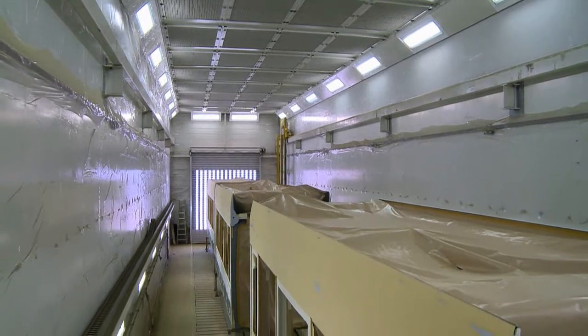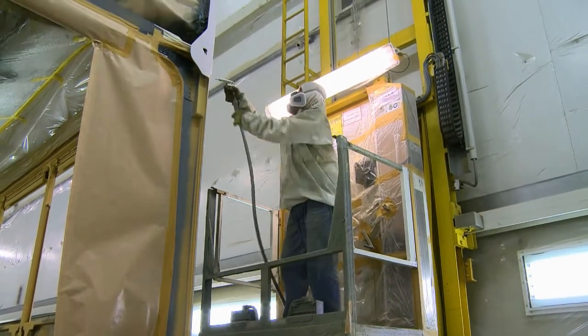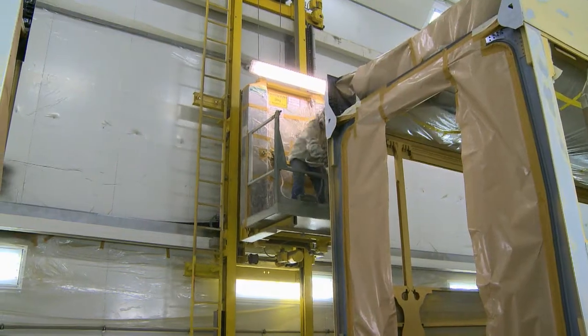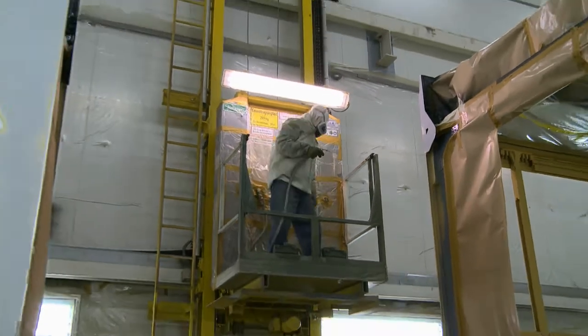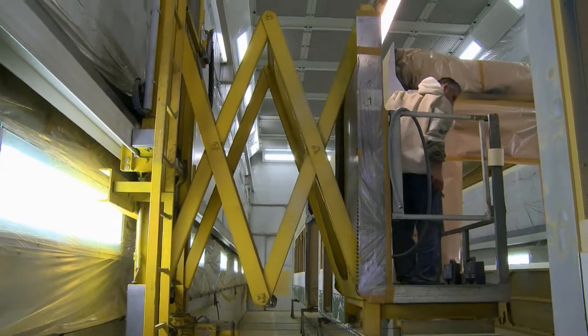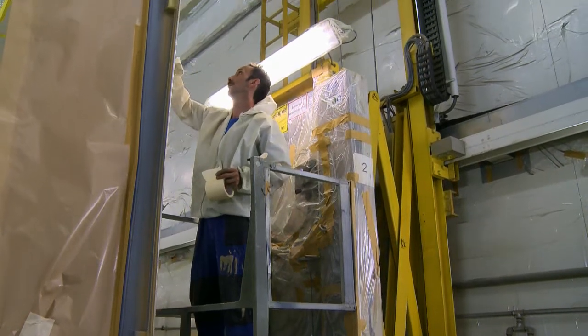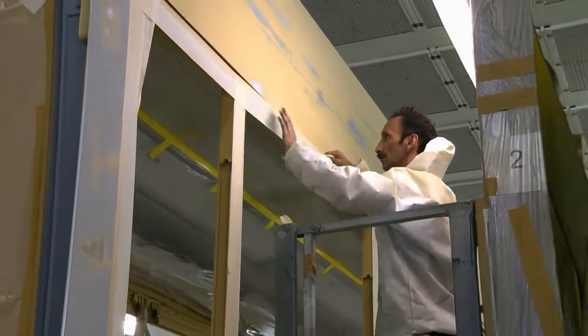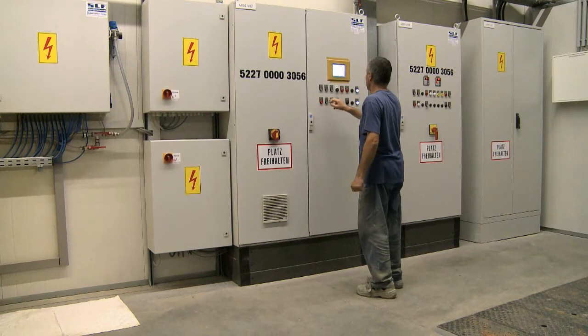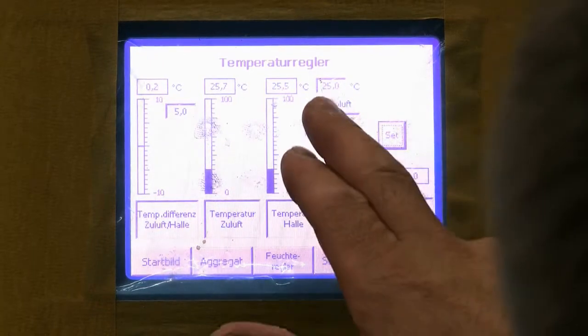The first step in the work process is to blow away impurities from the cars to create a perfect coating surface. These long fluorescent lamps illuminate every level of the work area at 1,000 lux. In this hall, the elevated work platforms travel along 28-meter tracks and have scissor-like extenders for varying their distance from the wall. These platforms can extend between cars by up to 2,810 millimeters to allow work on the ends of the cars. Masking is also performed on cars slated to receive more than one color of paint. The cabin is switched into coating mode from the control cabinet, and because operators occasionally use the touch panel while wearing work gloves, a protective foil has been applied to the screen.